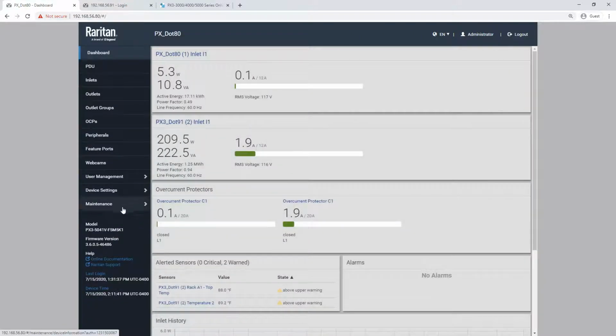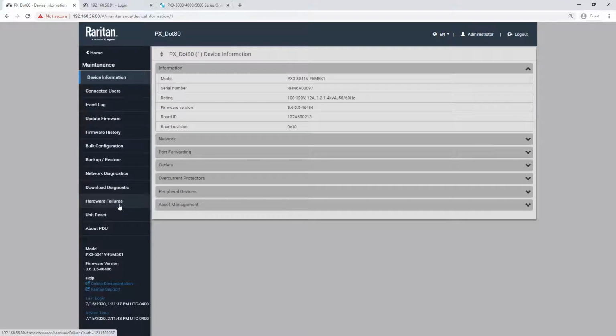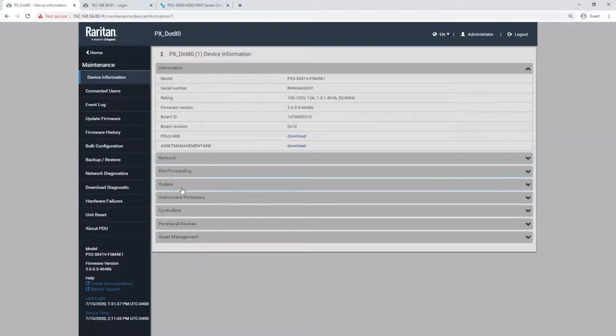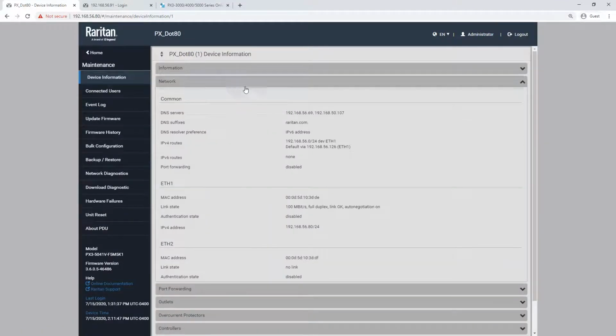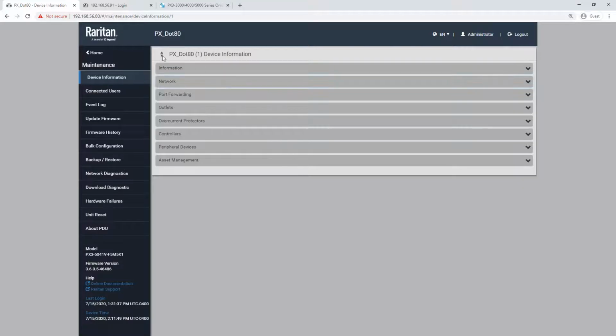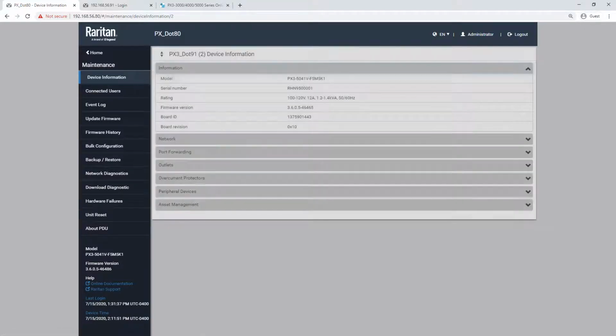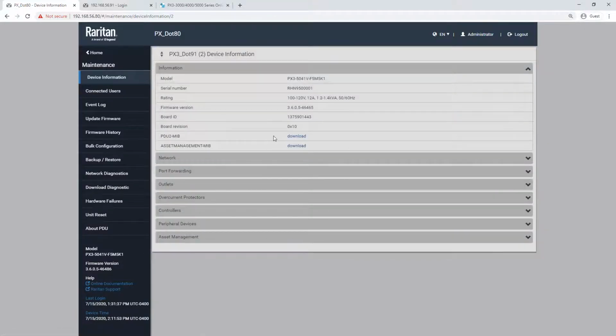Another thing I want to show here is maintenance, so we have device information. Sometimes it's beneficial for us to look at network info, and I can toggle to that secondary PDU and view its information. If I had other link units, I'd be able to select those as well. You can link up to 8 PDUs total, including the primary, so you can have up to 7 PDUs chained to it.